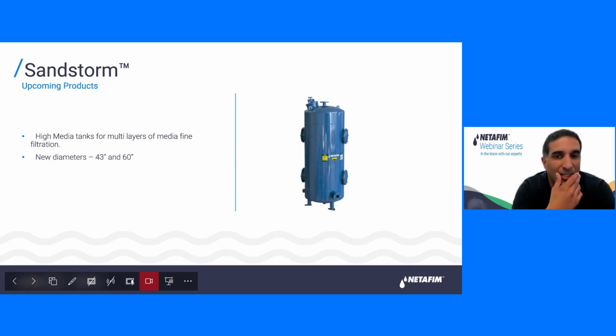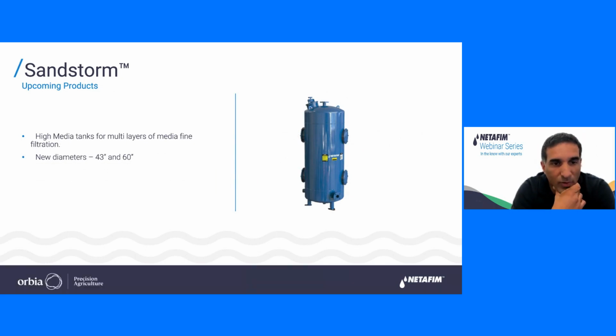So, novelties in the Sandstorm, new products that will be available soon. We will provide high media tanks, starting with a 43-inch tank that can be used for very fine filtration. If we're talking about the height of the media bed in the standard tanks of 40 centimeters, here we have 1 meter of media. So we have a deeper filtration, and we can handle water of very poor quality. So this will be available soon.